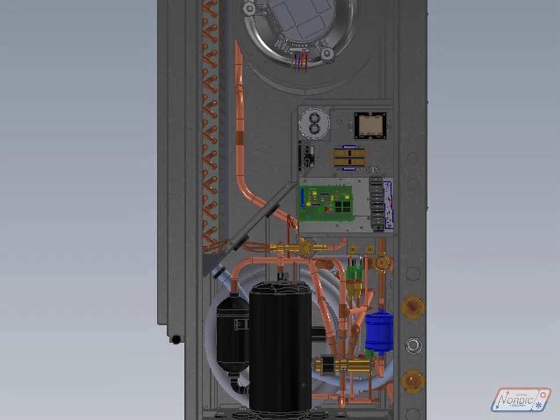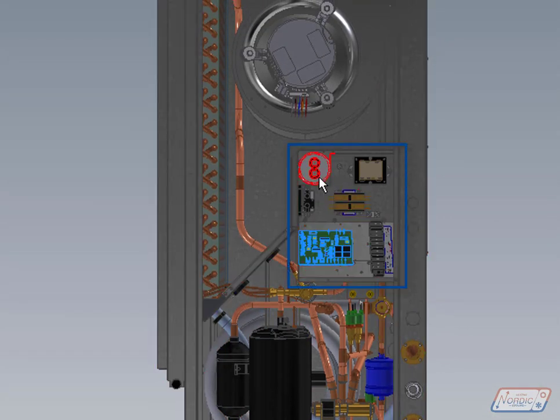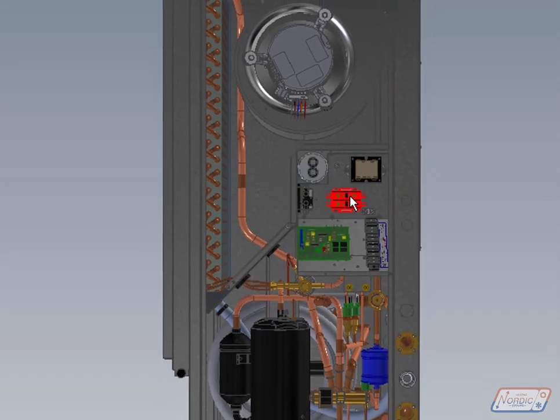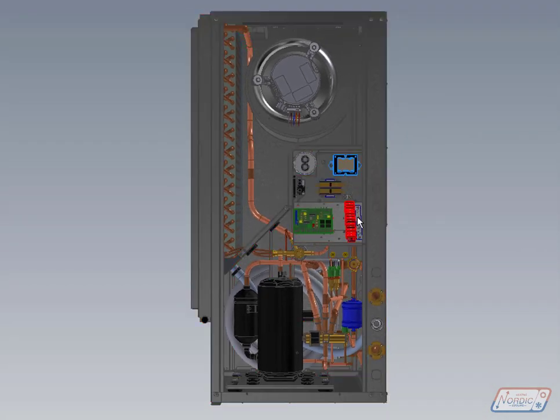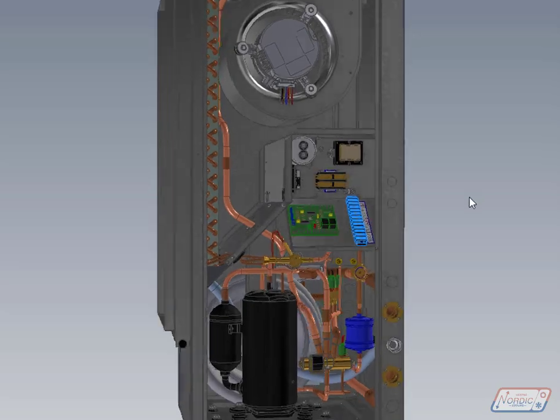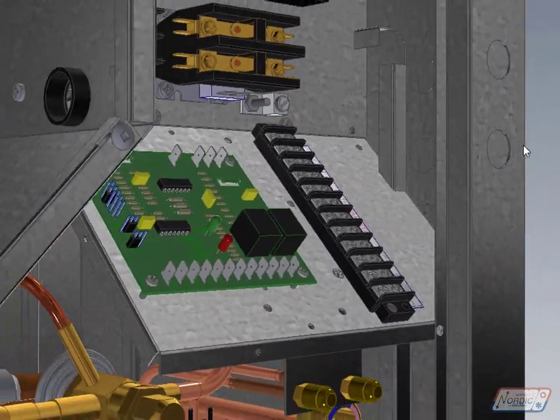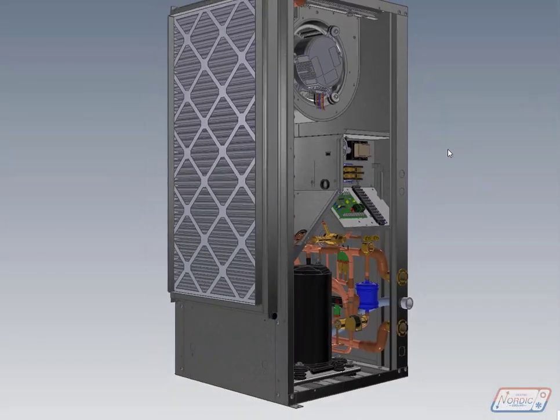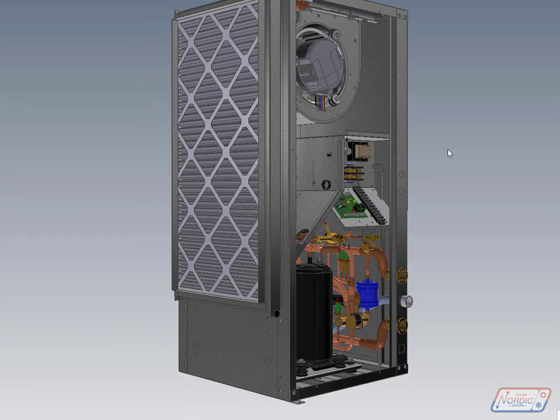The electrical box is accessible from the front, as I mentioned, and it's at a convenient intermediate height instead of at floor level, so a pleasure to service. The air filter, which I can show you here, is a pleated style air filter as opposed to a fiberglass air filter, and it's 1 inch thick rather than 2 inches on the residential series, due to, of course, the smaller unit size and reduced airflow on these units.